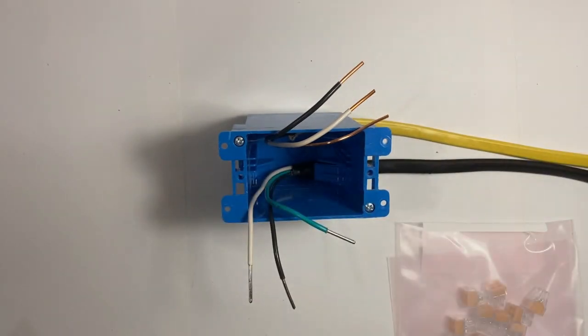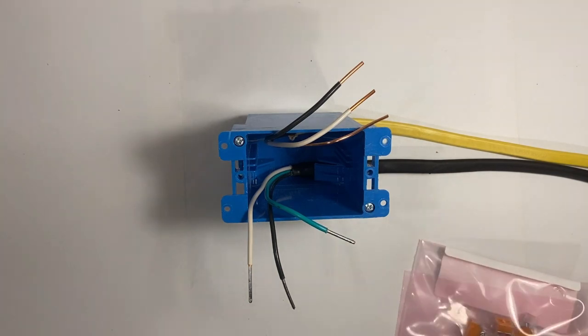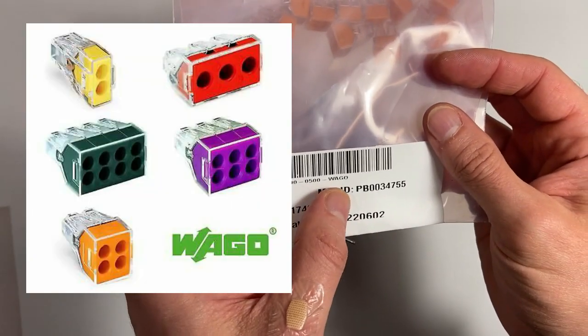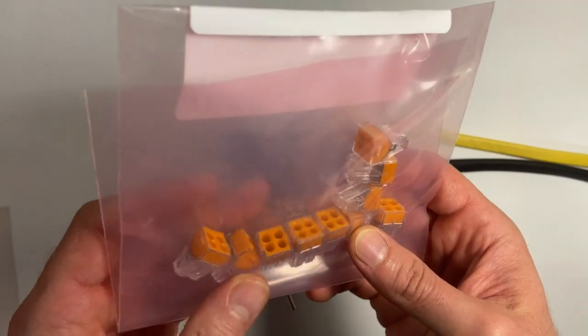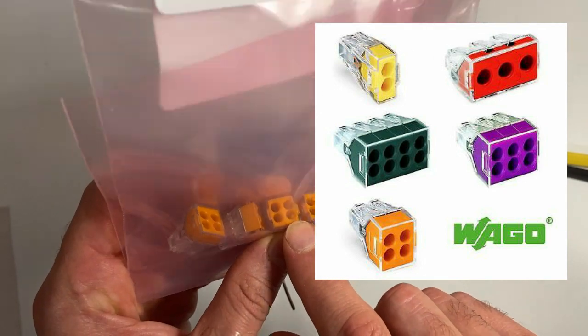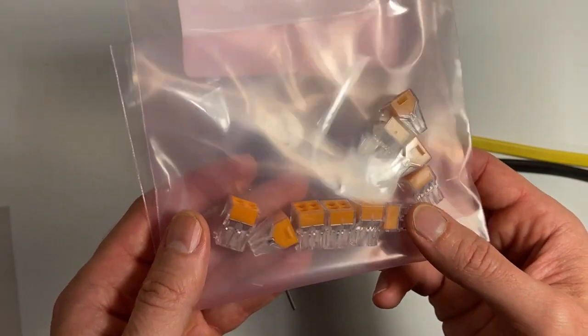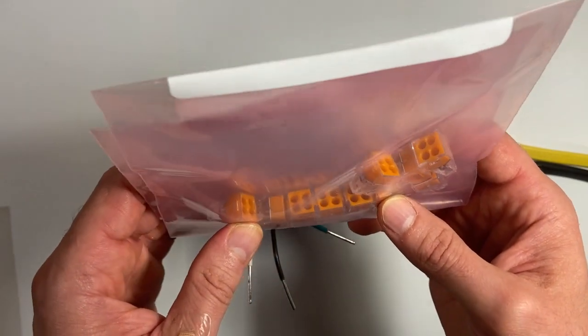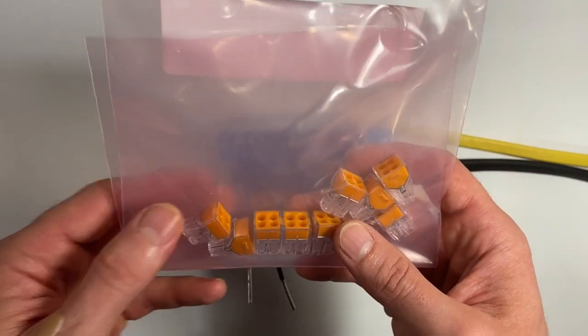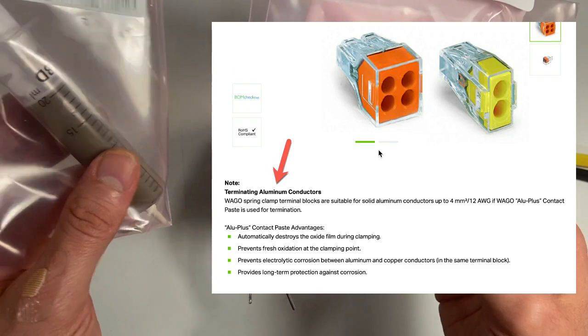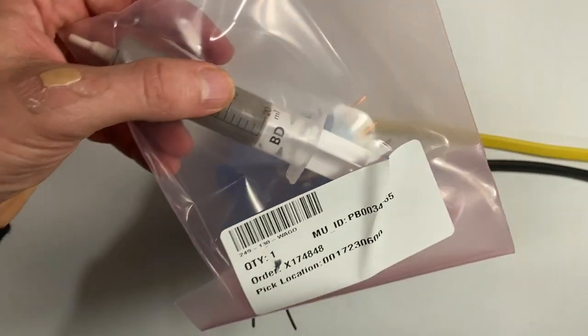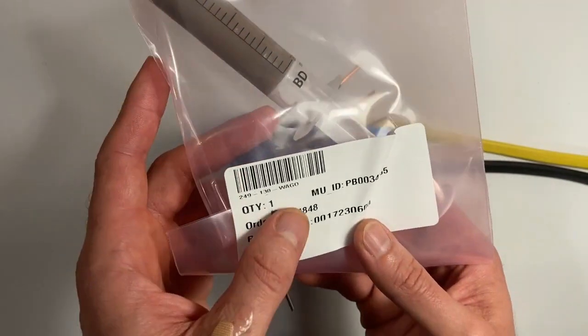And last but not least, these are Wago, W-A-G-O. They're made in Germany. They come in all different configurations. You may have seen them red color with just two ports. These are four-port ones. They are used for copper all the time. You can use 14 or 12 gauge copper in these. But according to the manufacturer, they are also approved to be used with 12 gauge aluminum wire.